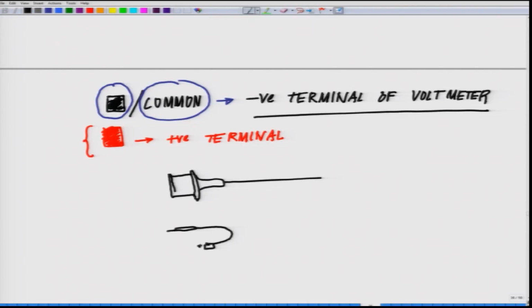If you look at the pH meter very carefully, the positive terminal is at the center, inside the connector. In other words, your positive is out here, and this rim what you see is where the negative is. So, try to realize, if sometime you want to do some kind of a trick, it is the center which is the positive and the outer periphery is the negative.